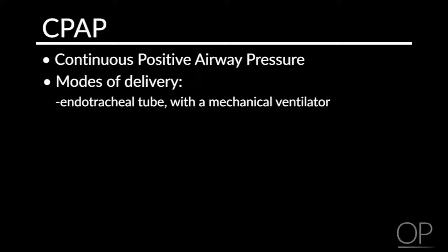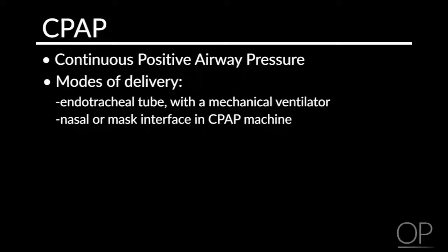CPAP stands for Continuous Positive Airway Pressure. It can be delivered in several different modalities, including via an endotracheal tube with a mechanical ventilator, through a nasal or mask interface in a CPAP machine, or via a bubble CPAP system, which I'll be showing you. I'll be using equipment to set this system up that should be readily available. However, you may need to modify the equipment and resources based on what you have available in your institution.